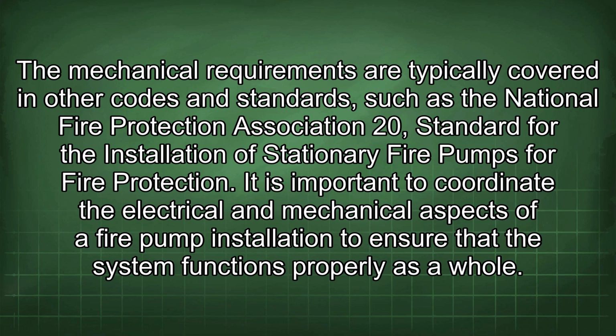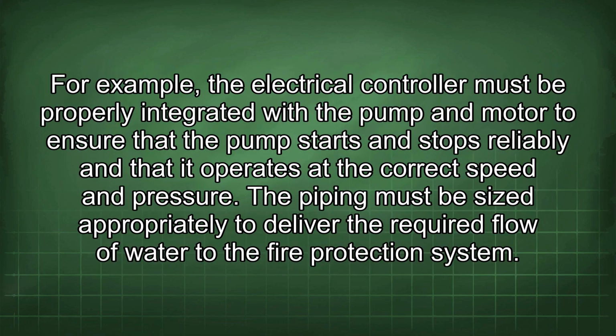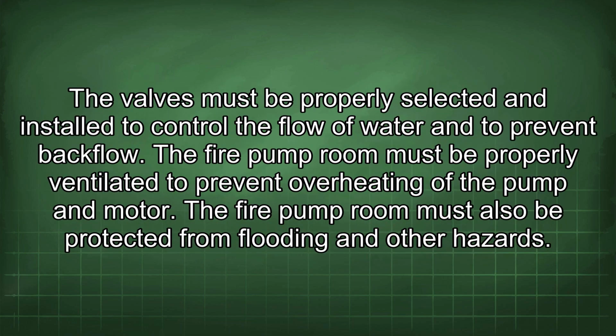It is important to coordinate the electrical and mechanical aspects of a fire pump installation to ensure that the system functions properly as a whole. For example, the electrical controller must be properly integrated with the pump and motor to ensure that the pump starts and stops reliably and that it operates at the correct speed and pressure. The piping must be sized appropriately to deliver the required flow of water to the fire protection system. The valves must be properly selected and installed to control the flow of water and to prevent backflow. The fire pump room must be properly ventilated to prevent overheating of the pump and motor. The fire pump room must also be protected from flooding and other hazards.